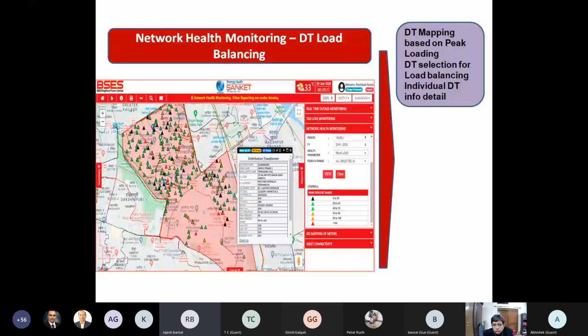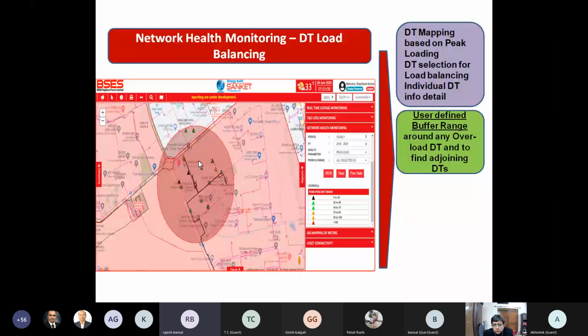If a transformer is overloaded, look into the next 500 meters. With just a click, check which transformer is underloaded in that range. Can we transfer the load from there? That's what we are doing. So you are saving a transformer, saving your no-load losses, loading your underloaded transformer, and reducing your technical losses.